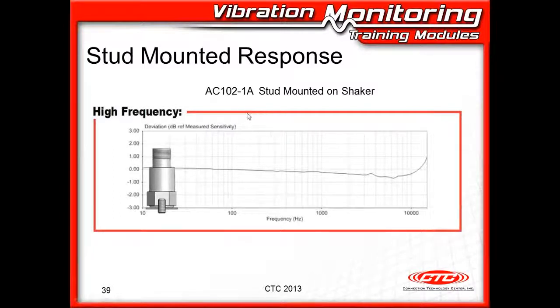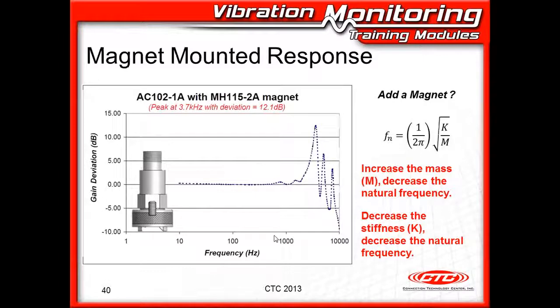Here's the high frequency response of an AC102 100 millivolt per g standard general purpose sensor stud mounted on our shaker system. So I've got it stud mounted, and we're sweeping from 10 hertz to 20,000 hertz. And this is still within 1 dB. This is a really good response. So we've got this great response, we've got a nice sensor, and then we're going to attach a nice curved surface 2-bar magnet to it and repeat this test. And what happens is you lower the resonant frequency to around 3.7 kilohertz or 4 kilohertz, somewhere in that region. Because you've lowered this resonant frequency, your usable frequency range tops out at about 2,000 hertz.